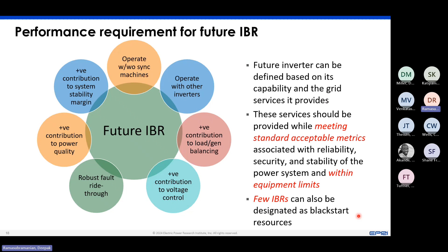Of this, there can then be a subset of inverters that might be black start resources. Note that grid forming doesn't equate to black start. A synchronous machine today is not necessarily a black start plant—not every synchronous machine plant is actually black start capable. You need special equipment inside the plant to become black start capable.